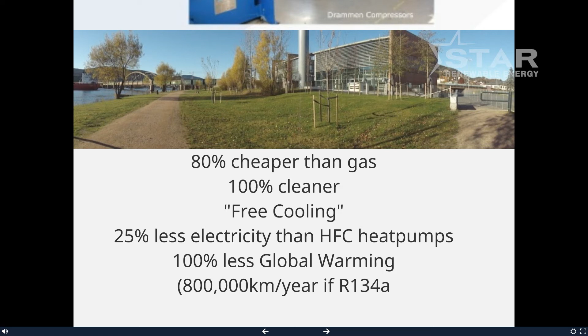Throughout the project, we've been saying to them, try and find some cooling opportunities. We're actually throwing away 10 megawatts of cooling back into the fjord. That's enough for 10 football stadium-sized data centres. That's a massive sales opportunity. It's probably at around about 30 euros per megawatt hour of cooling. It would be round about 2.4 million euros per year. So that's a significant opportunity to improve the economics.